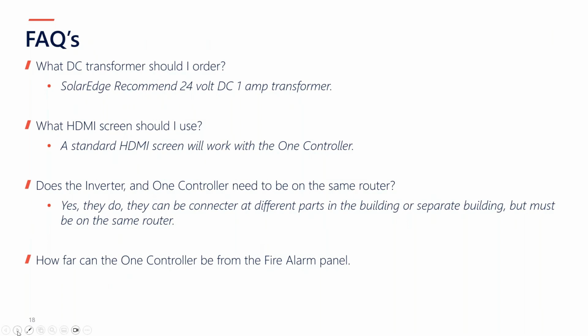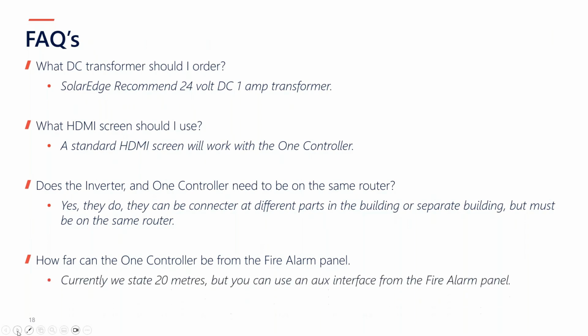So how far can a one controller be from the fire alarm panel? Currently we state 20 meters, but you can use an auxiliary interface from the fire alarm panel. The fire alarm panel is very clever now - they can use different means of extending the range, and you can use that.